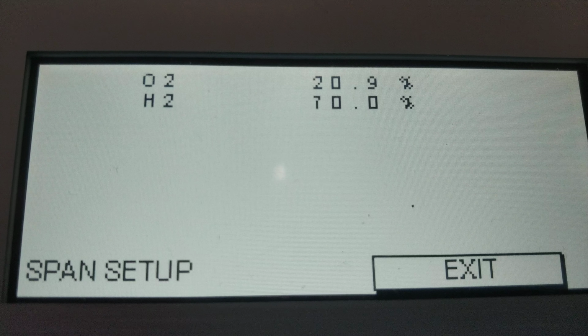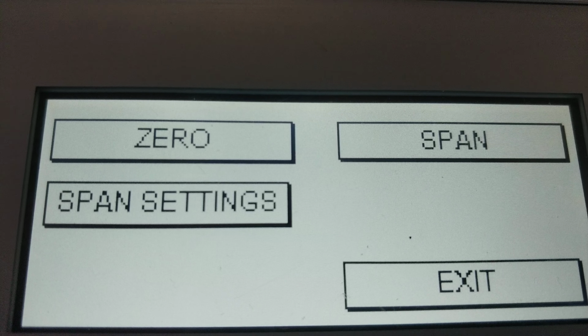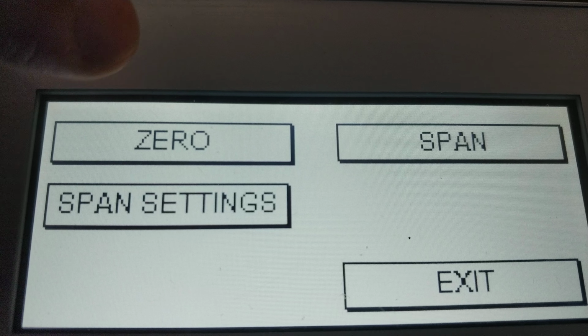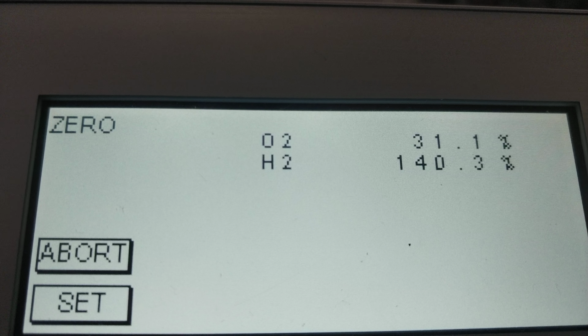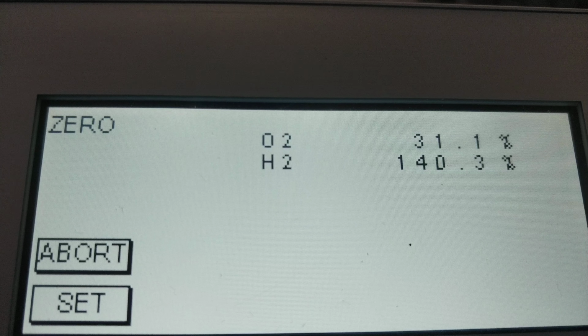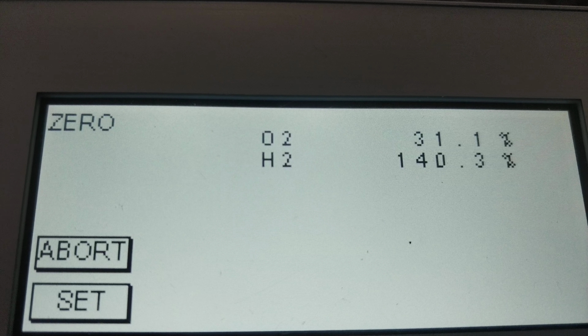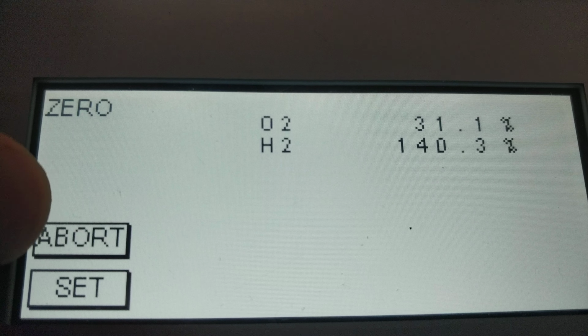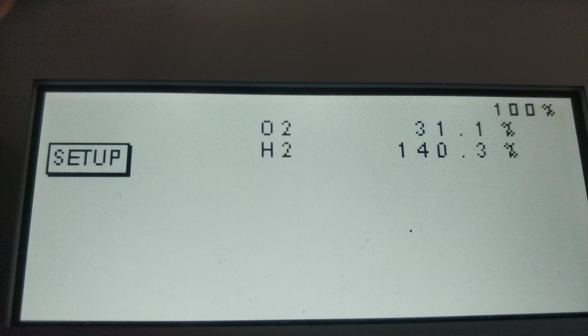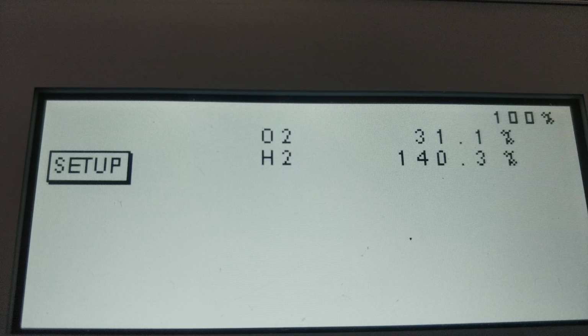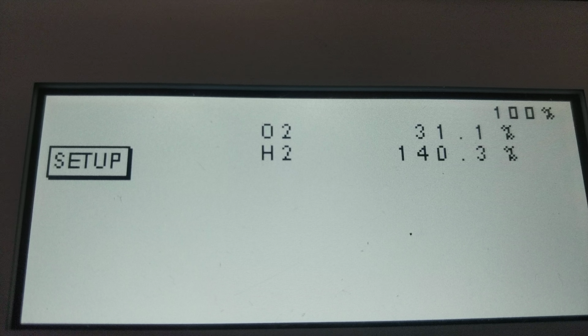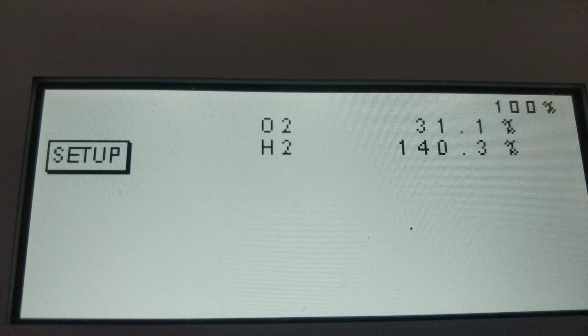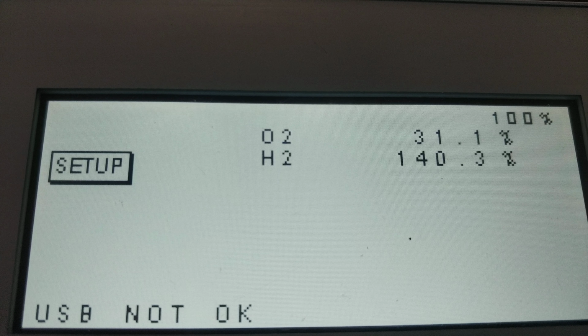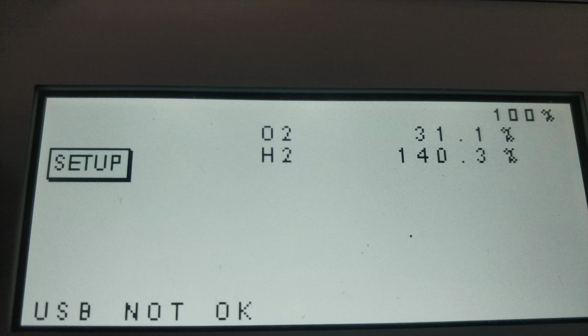With that, the next thing we want to do is a 0 and a span accordingly. So we're going to do a 0, let it go for a couple of minutes, and then hit set. I don't have any gas running right now, but just to give you an example, we would let the ambient air come through, we'd let the pump in the analyzer let the gas flow through the analyzer, and then we would press the set button. I'm just going to press abort for now. The same thing, just gotta wait a couple of seconds here. We would do the same thing for span. We would go to span and press set after a couple of minutes once we ensure a sufficient amount of gas is flowing through the analyzer, and then that should fix your issue.